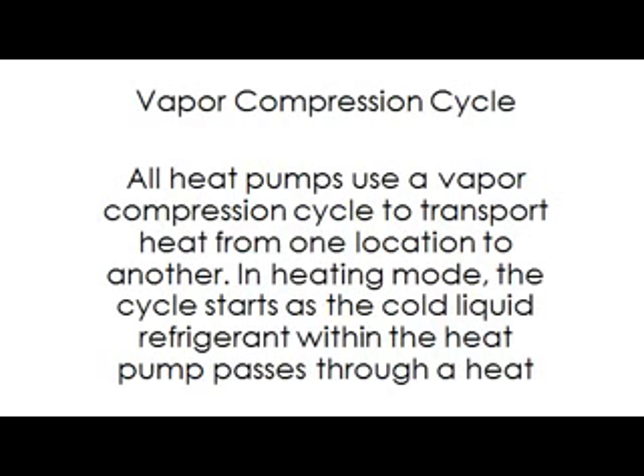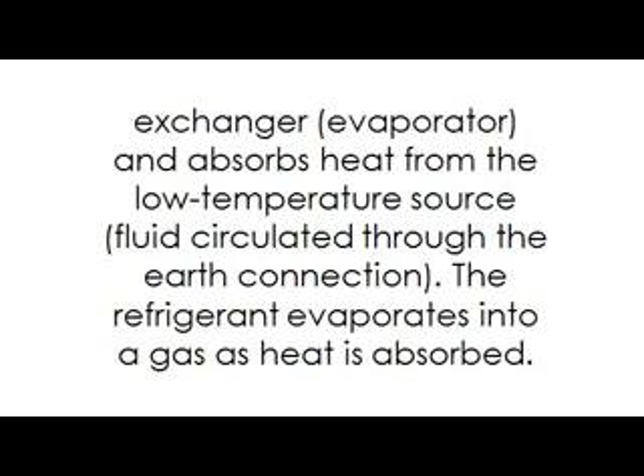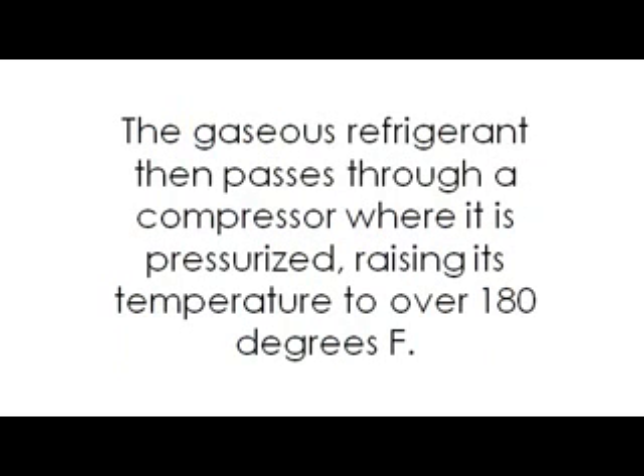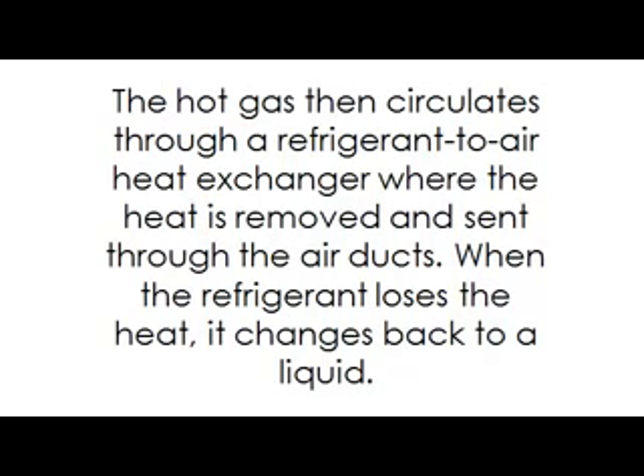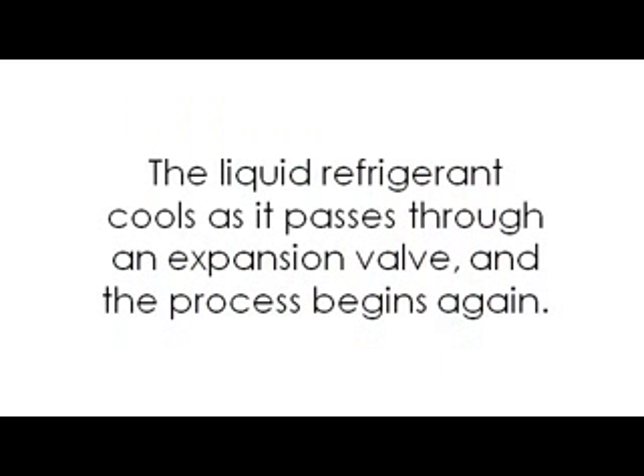Vapor compression cycle. All heat pumps use a vapor compression cycle to transport heat from one location to another. In heating mode, the cycle starts as the cold liquid refrigerant within the heat pump passes through a heat exchanger or evaporator and absorbs heat from the low-temperature source, fluid circulated through an earth connection. The refrigerant evaporates into a gas as heat is absorbed. The gaseous refrigerant then passes through a compressor where it is pressurized, raising its temperature to over 180 degrees Fahrenheit. The hot gas then circulates through a refrigerant-to-air heat exchanger, where the heat is removed and sent through the air ducts. When the refrigerant loses the heat, it changes back to a liquid. The liquid refrigerant cools as it passes through an expansion valve, and the process begins again.